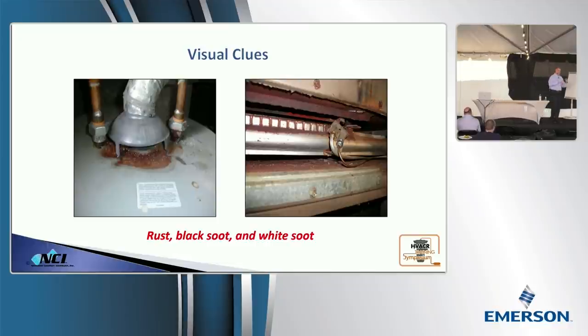When you look at the combustion process, if everything works perfect, we get carbon dioxide and water vapor, right? It looks so innocent. But what happens when that full conversion doesn't take place? We get nasty stuff like carbon monoxide, and we also get carbonic acid. So when you see flue gas condensing on a metal surface, it will eat it up. It's not just a delta T. There should be no acidic properties in that water, unless you're from California. But as you start to get into the opening around that, that is flue gas condensing on that hood.